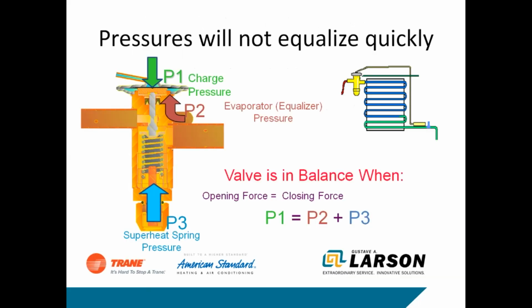Okay. If you're using an expansion valve, the valves that we put on our equipment, the pressures do not equalize very quickly. So in other words, if you're running a system and you've got, say, 110 on the suction and 350 on the high side, and you shut the system off, it's probably going to stay there. The 110 and the 350 are not going to change. These are hard shut off expansion valves that we're using. They're externally equalized, but that doesn't mean that it equalizes the pressure. That means that it's referencing the exit pressure of the evaporator to properly flow the refrigerant into the system. So just remember, when we're doing compressor tests and we're looking at compressors, if the pressures don't equalize in the system with an expansion valve, that's perfectly normal. Okay.